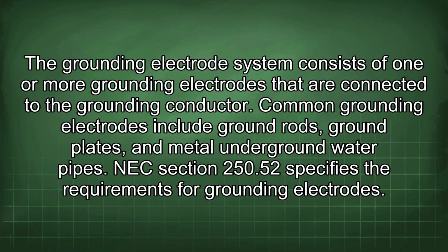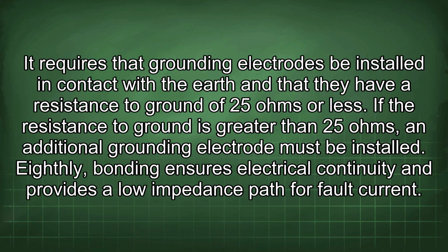The grounding electrode system consists of one or more grounding electrodes that are connected to the grounding conductor. Common grounding electrodes include ground rods, ground plates, and metal underground water pipes. NEC Section 250.52 specifies the requirements for grounding electrodes. It requires that grounding electrodes be installed in contact with the earth and that they have a resistance to ground of 25 ohms or less. If the resistance to ground is greater than 25 ohms, an additional grounding electrode must be installed.